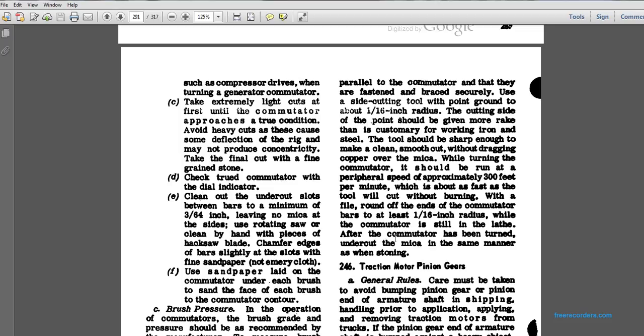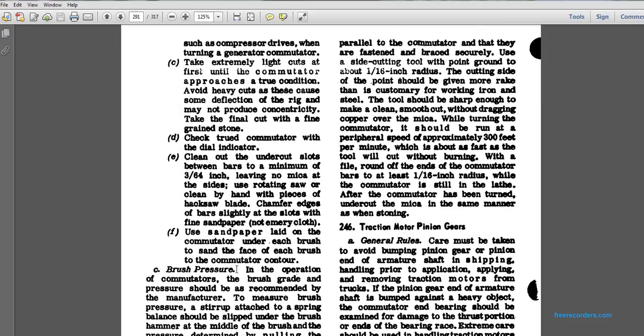Take extremely light cuts at first until the commutator approaches the true condition. Avoid heavy cuts, as they cause some deflection of the rig that may not produce concentricity. Take a final cut with a fine grade of stone. Check the true commutator with the dial indicator. Clean out the undercut slots between the bars to a minimum of 3/64 of an inch. Leave no mica on the sides. Using a rotating saw, clean, and finish by hand with a piece of hacksaw blade. Chamfer the edges of the bars slightly at the slots with fine sandpaper or non-emery cloth.